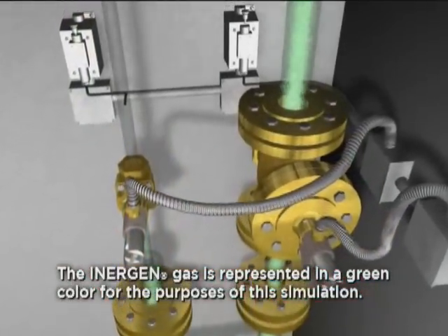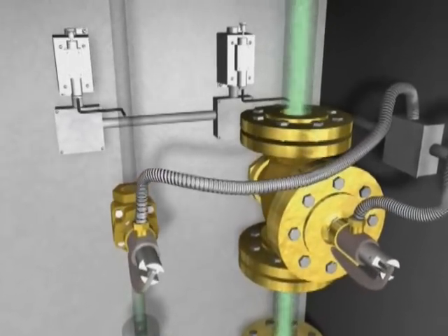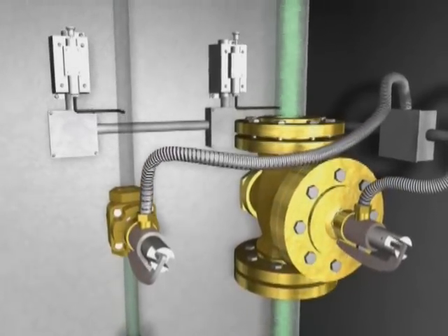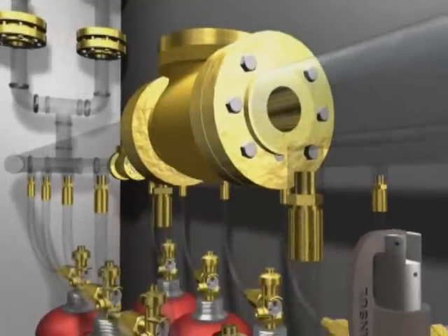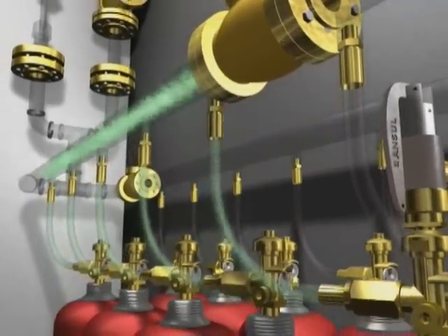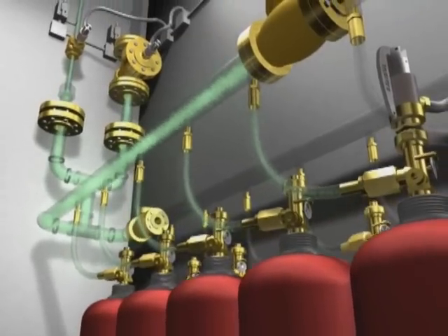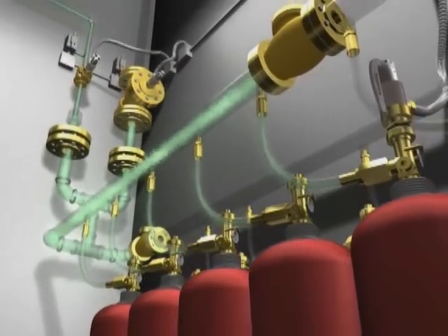In places where Inergen is protecting more than one room, a unique selector valve is used to direct the system discharge into the appropriate zone. A check valve is used in a selector valve system to separate the discharge of one zone from the other, preventing the Inergen flow back to the main system cylinders.